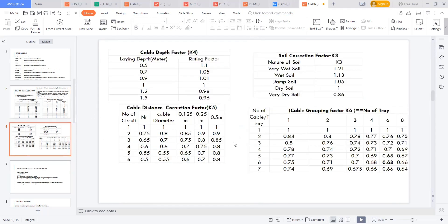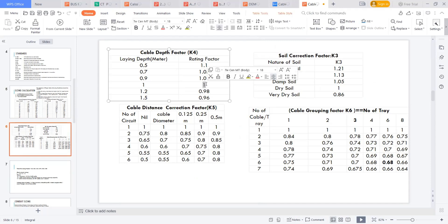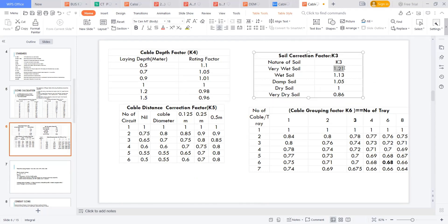So this 930 amps, again I am looking into the depth factor. If I am laying this at a depth of one meter, the multiplication is one, so it remains as 930 amps. And I laid this in very wet soil, so then 930 amps into 1.21. That gives me 1125 amps. Now my current rating increases to 1125 amps.